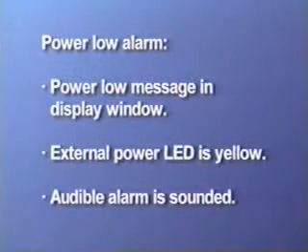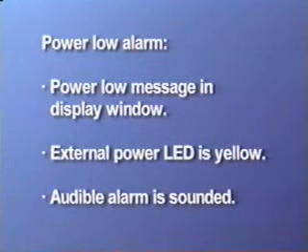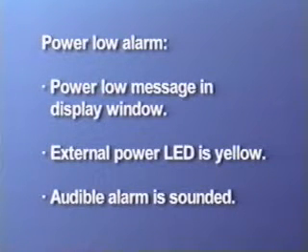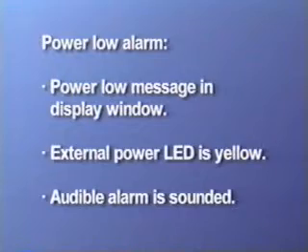The power low alarm occurs when the ventilator is operating on external battery power and the voltage drops to the low level. When a power low alarm occurs, the power low message is flashed in the display window, the external power LED is displayed yellow, and the audible alarm is sounded. To reset the power low alarm, press the silence reset button twice.